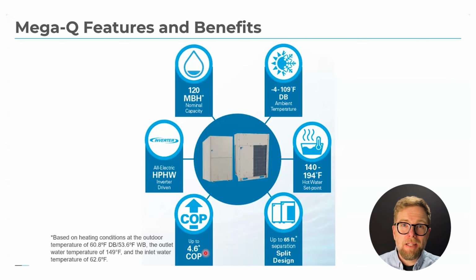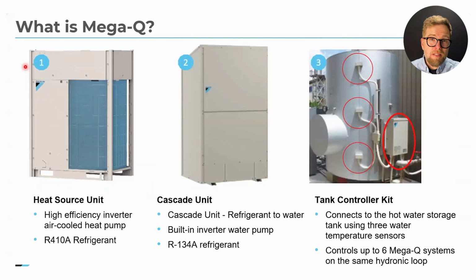Each MegaQ is 120 MBH, which is a 10-ton system, and you can hook 6 together on a single water loop for a total of 720 MBH. That means more than enough output for large multifamily residences, hotels, and commercial buildings. And it does look very similar to the VRV units that we are using right now. The control logic in these systems is incredibly sophisticated.